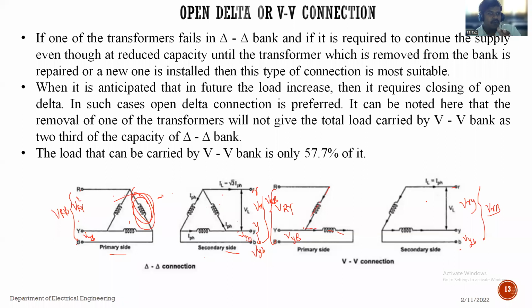But due to that open circuited transformer, meaning one of the three single phase transformers is removed, suppose all three together carry a load of 10 kVA. It will carry a load of 10 kVA if all three transformers are connected.